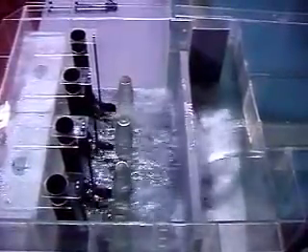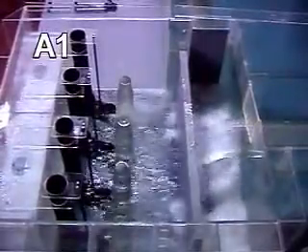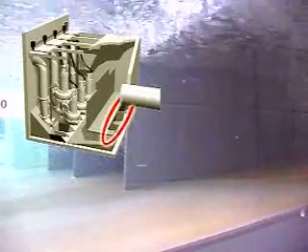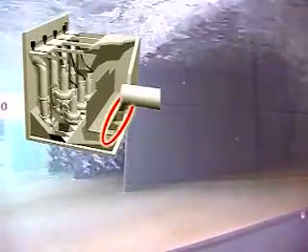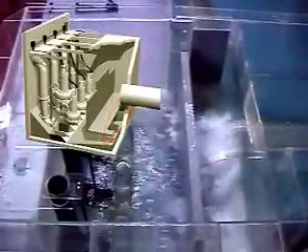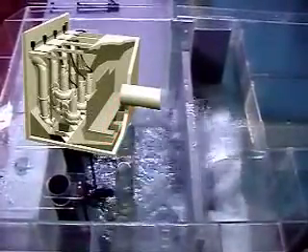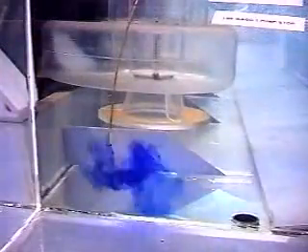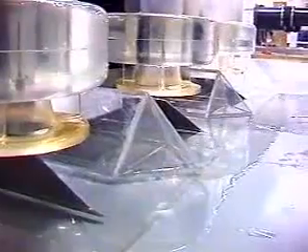ITT Flygt has developed a number of sump designs according to these criteria. For example, the central front high-level entry design, type A1. A specially designed baffle wall minimises the air entrainment due to falling water. The flow from the inlet pipes impinges on the baffle wall and then flows down into the inlet chamber through the slot in the floor of the baffle. This slot distributes the flow evenly towards all the pump inlets with a minimum of pre-swirl. Equipping the sump with splitters and benching is often beneficial for pre-swirl and prevention of sediments.